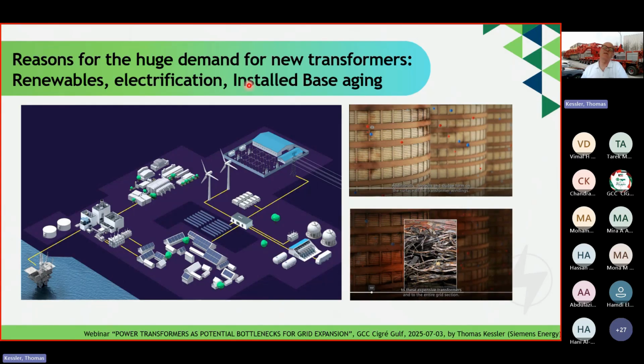And this effect is the installed base aging. In a transformer, besides high voltage, we have biomass like paper, wood, and oil. Especially in your region, transformers are exposed to high temperatures, sand, storms and sun. So we have a significant aging impact, and this impact can, over time, increase the risk of failure. So if we want a resilient and reliable grid that is developing, we have to consider all aspects: the renewables, the electrification, and the aging of the installed base.